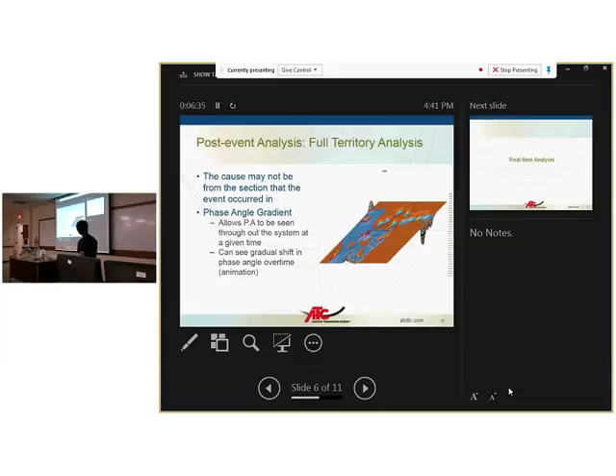This right here is a phase angle gradient that I scripted out using VBA - if anyone's familiar with it, it's a function within Excel. If you just go to the developer tab and press that VBA script, you can start programming stuff. What I did here was take a bunch of data points, the PMU data, extracted the PMU phase angle, and mapped it out throughout the grid.